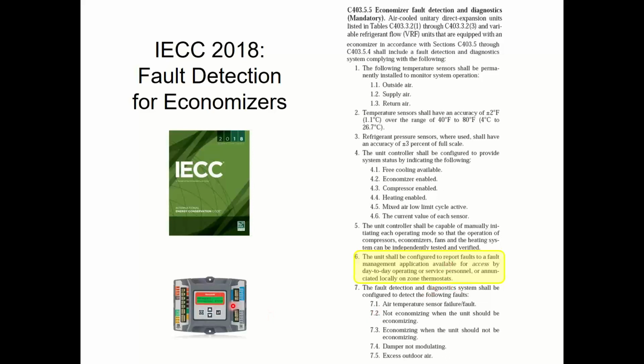So it cannot be the screen up inside the rooftop, because we know you're not going to go look at the rooftop screen every single day. It's got to push it down to the building automation system where it pops up on the computer screen, or it shows up as a text message on the building operator's phone, something to proactively notify them. Well, Ryan, what if I don't have a building automation system? I just got a little 10-ton rooftop unit and a regular thermostat, and that's all I got. That's fine. There's an or on here. Or annunciate it locally on the zone thermostat. So if you don't send it to the BAS, you can send it to the actual thermostat on the wall that the building occupants will see.